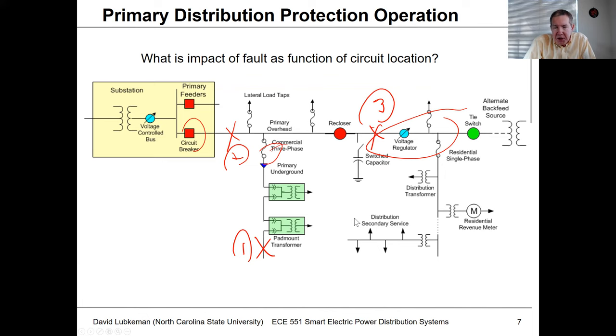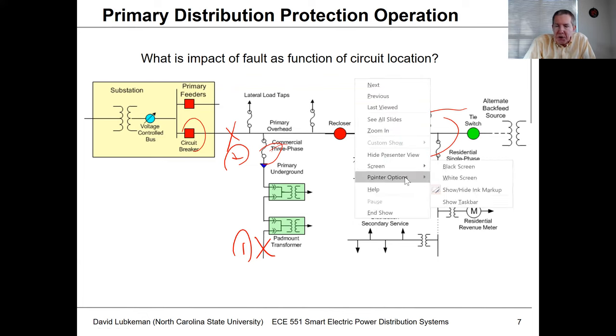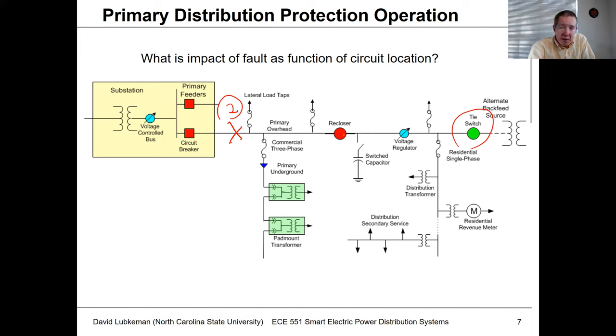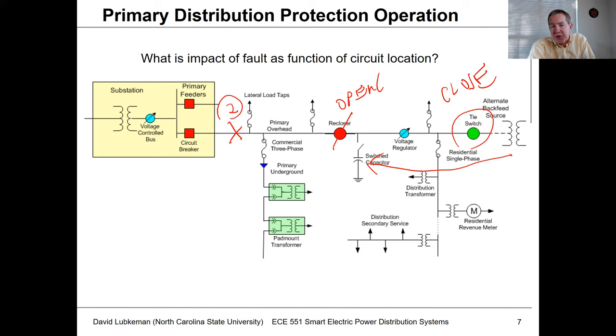For this circuit scenario number two — if we have a fault here — what if we had automation where I could operate this tie switch automatically? I could open up this recloser, close this switch, and restore service to all these customers below the recloser while we're waiting to fix the fault at location number two. That could be done manually by a crew or through automation. Those are the types of things we're going to be talking about — getting a baseline for expected reliability metrics and then what we could do to improve those metrics.